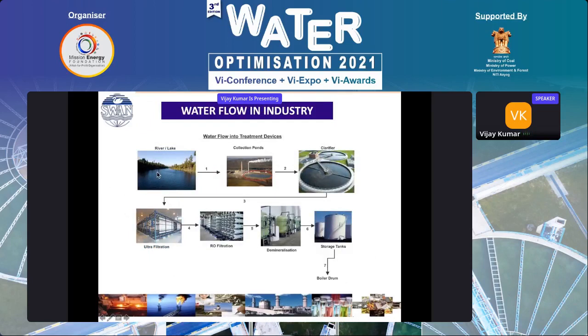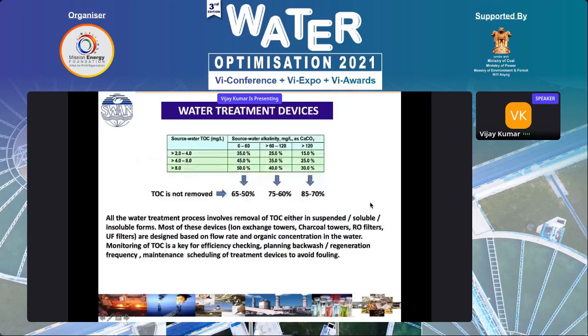If you see the water flow in general industry or in a power plant, for example, from rivers and lakes, whatever water you are getting goes to your clarifiers, then to ultrafiltration, then RO filtration, then demineralization, then storage tanks, and then goes to the boilers. This is one stream. Another stream is from the clarifiers to the cooling water inlet bay, and then it is used for cooling towers.